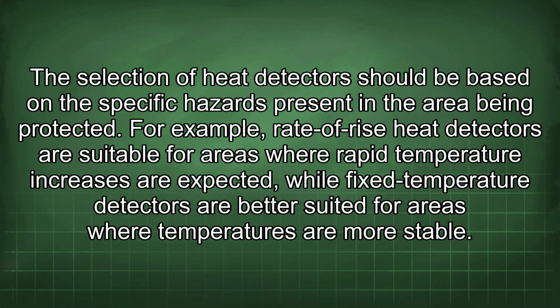The selection of heat detectors should be based on the specific hazards present in the area being protected. For example, rate of rise heat detectors are suitable for areas where rapid temperature increases are expected, while fixed temperature detectors are better suited for areas where temperatures are more stable.